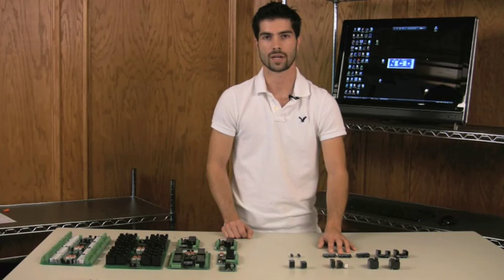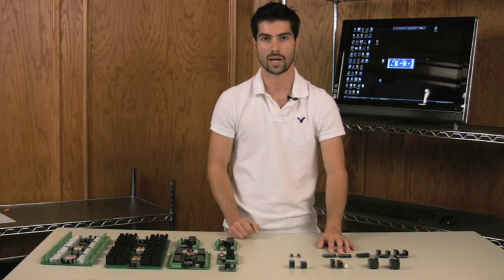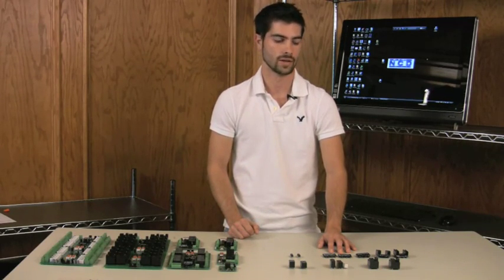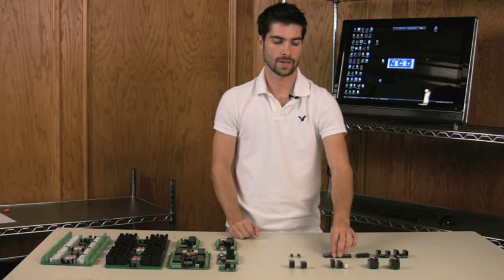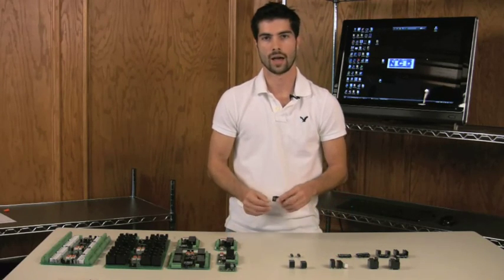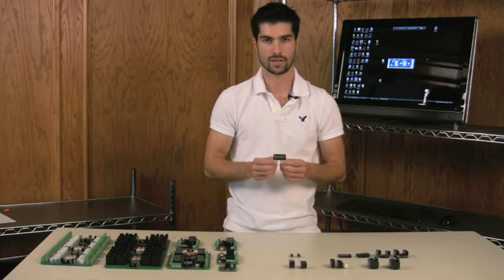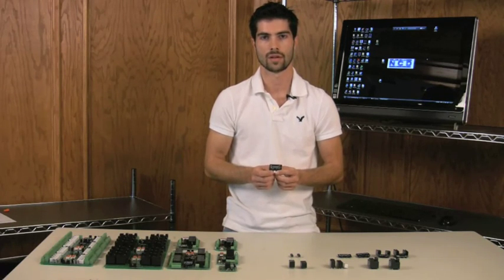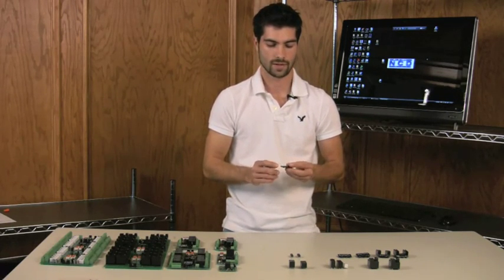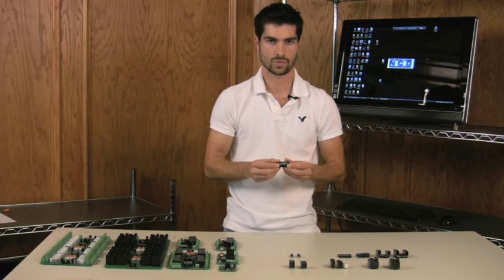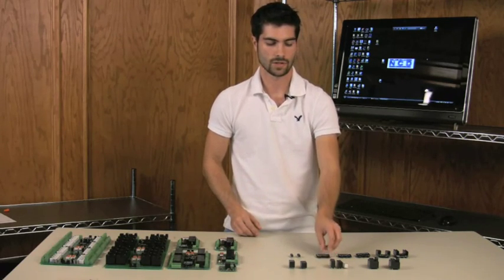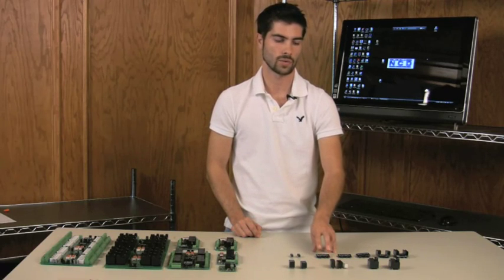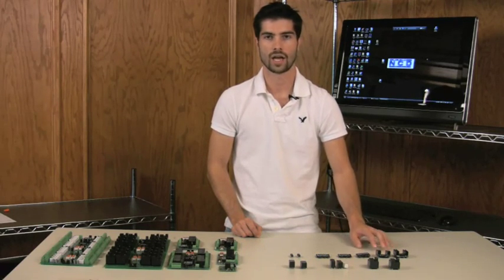Whenever you go to select a solid state relay controller on our website, towards the bottom of the page it will ask you which type of solid state relay you want. Be sure and review all of the information. These things have what we call a minimum switching current, meaning they are load dependent. I believe all these have a minimum load of 0.06 amps. So you want to make sure that you're switching more than that whenever using these. You want to know whether or not you're switching resistive or inductive loads, and you'll have to know the amperage of the device that you're switching.